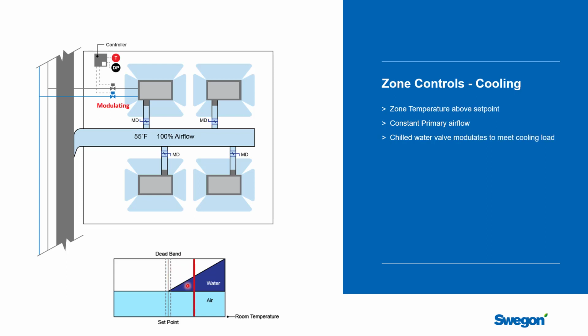And then we're going to have an increase in internal heat gain. And so you can see that we're no longer satisfying the space. The temperature has moved away from the set point, the deadband area. And so now what happens is the controller will start to modulate that chilled water valve to the beams to meet that load. And it will be able to vary the flow rate through here to come up to a balance point and zero in on it.